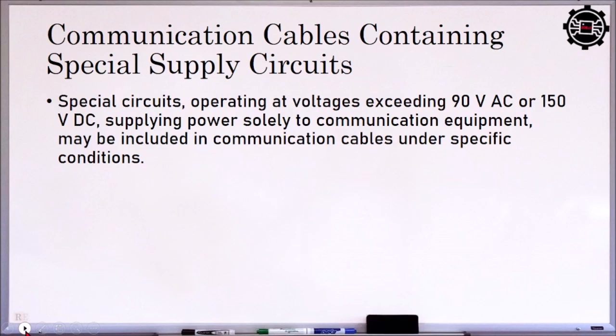Then communication circuits brought out of such cables, if not terminating in a repeater station or terminus office, should be protected to limit the voltage of the communication circuit to 400 volts to ground in the event of cable failure. So ibig sabihin, in case na may trouble or na-grounded yung supply circuit for the communication cable, so yung kanyang voltage to ground, or kanyang ground fault voltage should not be more than 400 volts. So dapat maglagay ng protection to limit that voltage from exceeding these 400 volts.